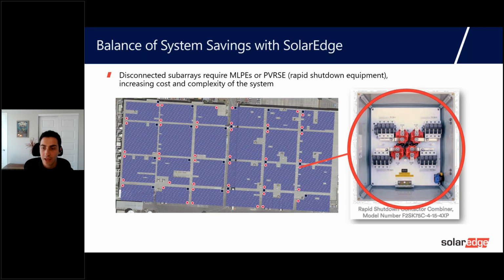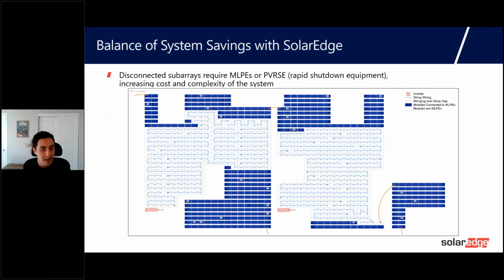One option shown on the screen is to use PV rapid shutdown equipment, listed devices, whenever strings cross the gap between subarrays. You can see in the image here, this is a contactor combiner box. 1 to 2 of these devices is needed per subarray. The other option for NEC compliance is to use MLPEs on some of the modules, so not every module, but any module that is connected to an inverter in a different array or a different portion of the array. The image here shows how modules that are connected across a gap between 2 portions of the subarray are all going to require some type of RSD at the module level.